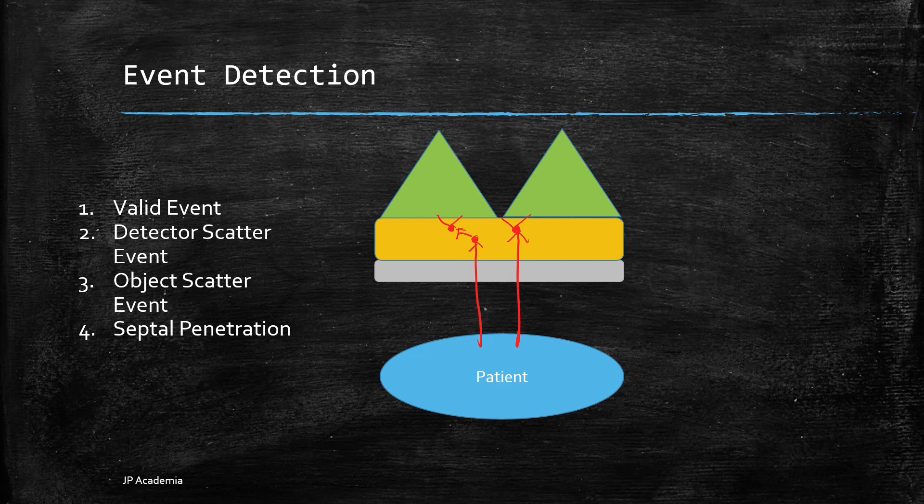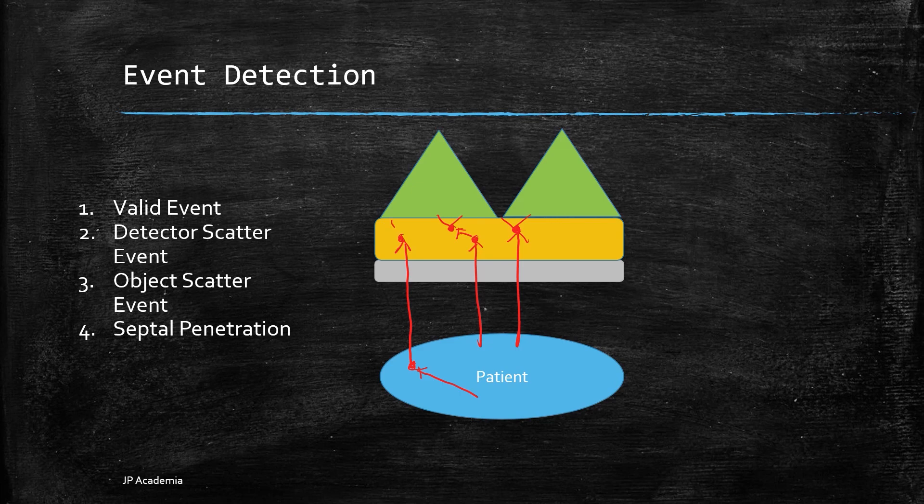Third event is the object scatter event, illustrated inside the patient before it interacts with your crystal. The gamma ray is not emitted toward the collimator holes but scattered within the body first, then it passes through the collimator and subsequently detected by the system.